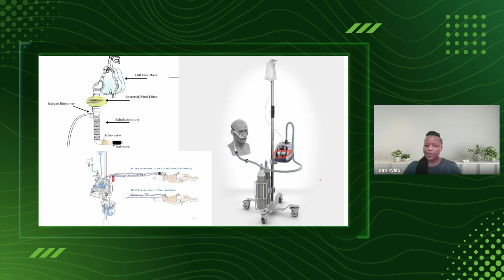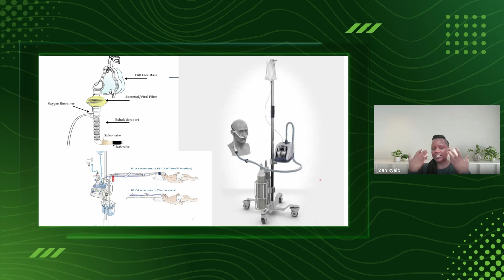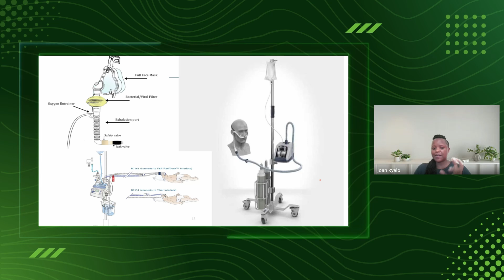Every high flow device should have that sort of setup, otherwise it's not high flow. I've also seen things in hospitals where somebody took a normal cannula and put it on a 60-liter flow meter at 20, saying this is high flow. It was very painful. You can literally damage the patient's upper airway because it's a cold gas, painful, and it dries up the mucosa. That's how you deliver high flow, through a heated system.